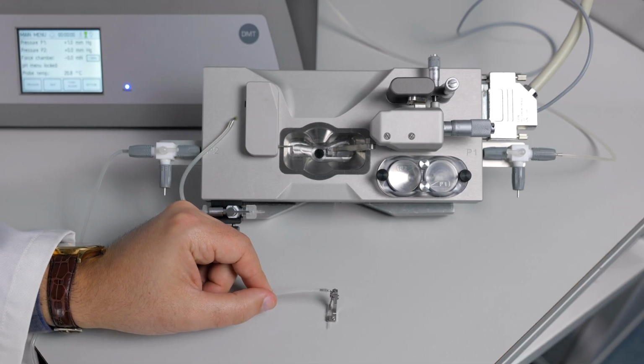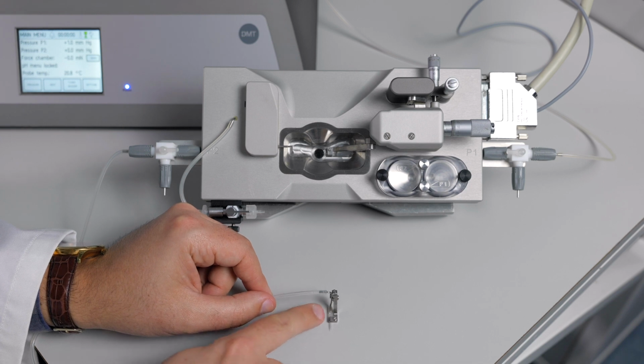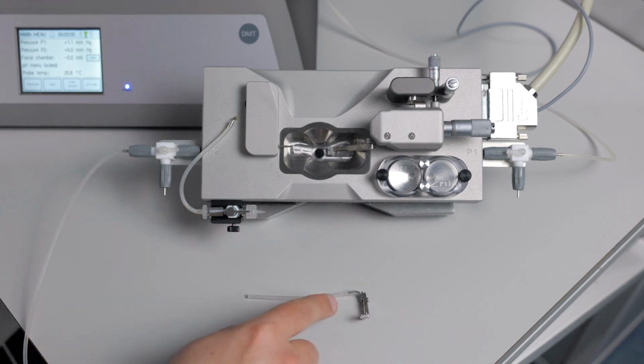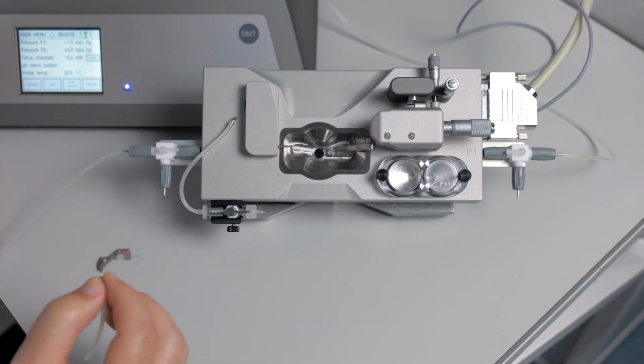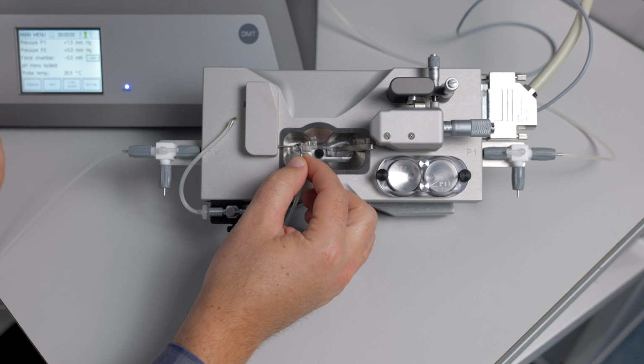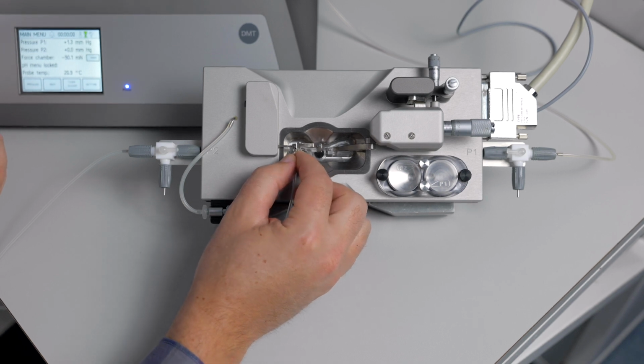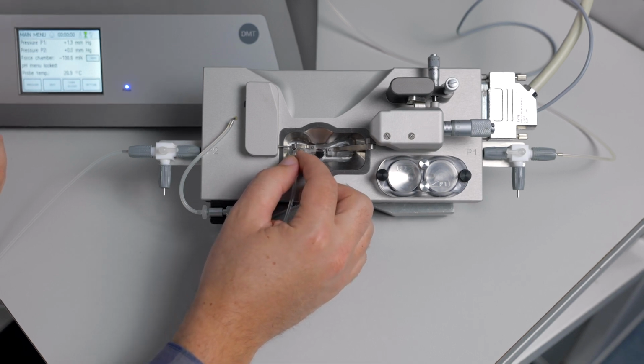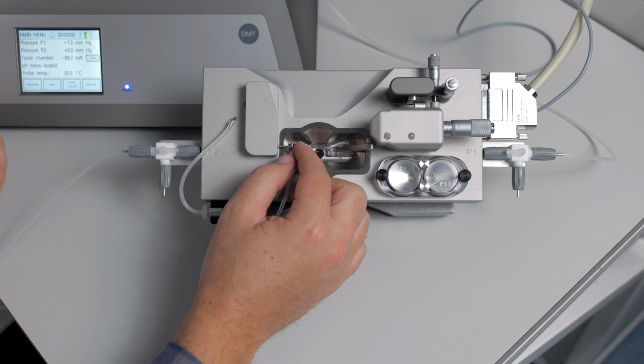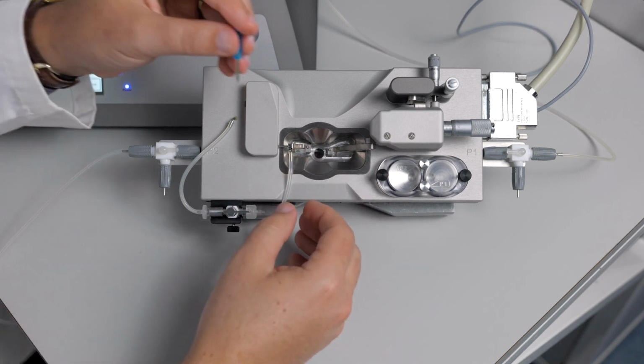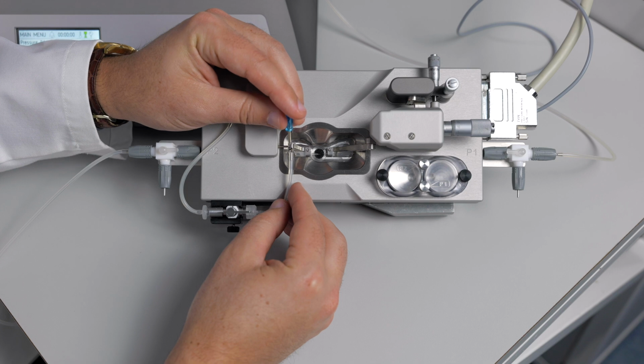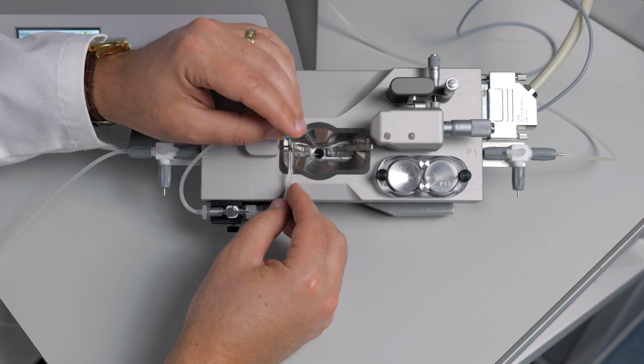Now the process is very similar to P1. You will loosen this fastening plate, which will expose the tubing and the cannula. You can then replace both sections. It's also a good idea to replace this additional section of tubing at the same time. You can now replace the P2 cannula mount on the transducer arm. You can now secure this mount in place using the screw and replace the tubing on the bottom valve.